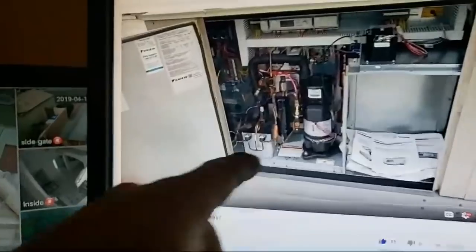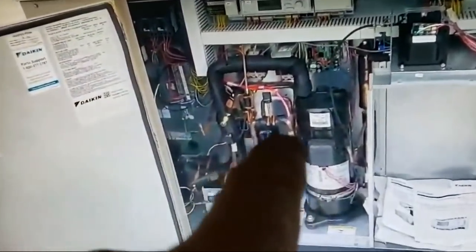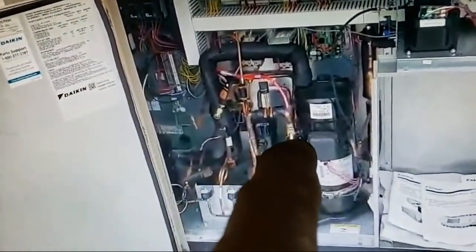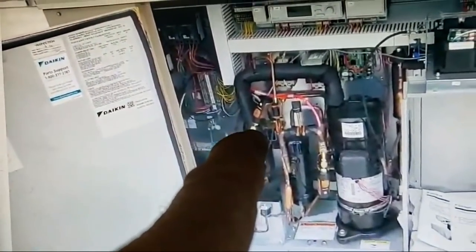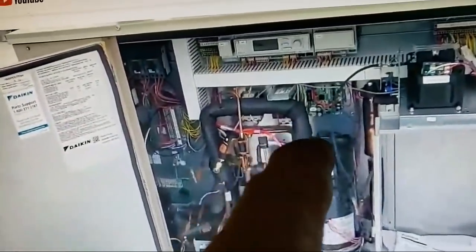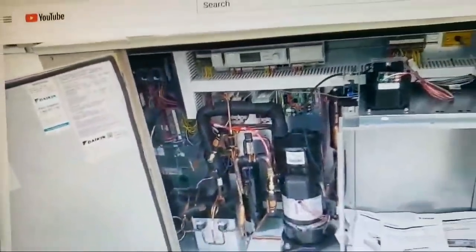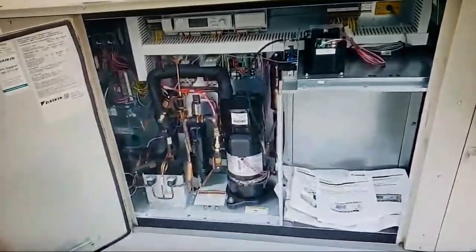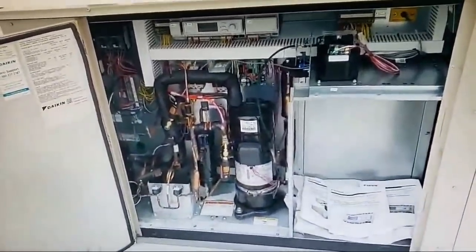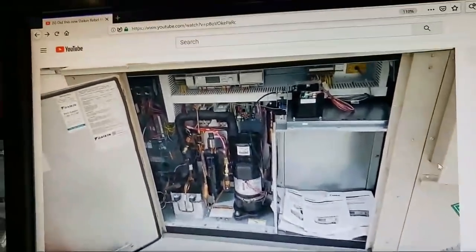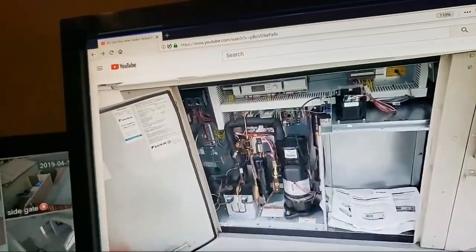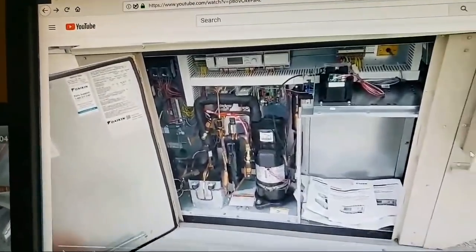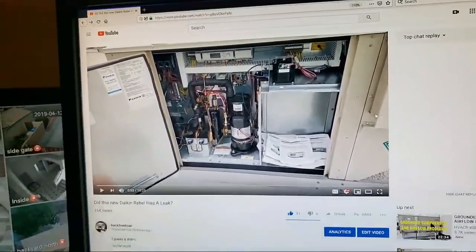He says that's even when I saw it go down to 12 psi in the suction before climbing over the next minute or two, they'll do that. It's don't expect normal stuff. It is a VRF. You got the variable compressor. This compressor is a rotary. Some guy chimed and said my ports are on the wrong spot, by the way. That's not. That's right on the discharge of the compressor. That right there is right on suction. Suction's on top on that compressor, by the way. That is a rotary, and it is variable speed entirely.